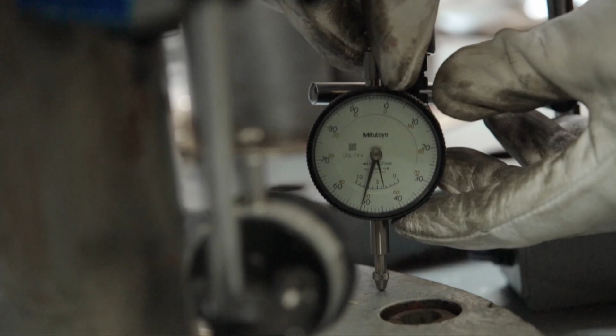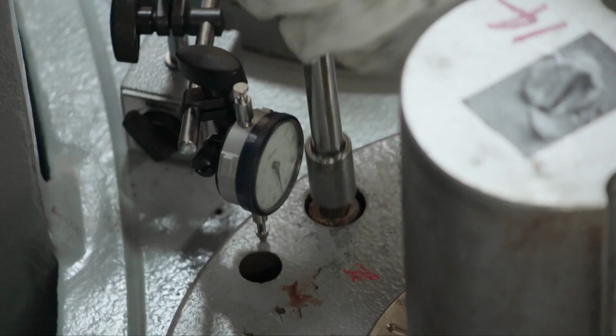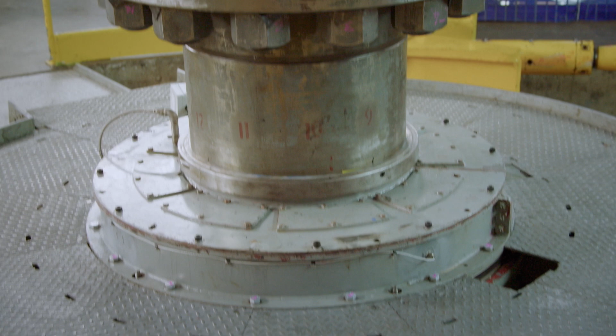We're just measuring the uplift on the reg ring just to make sure that when the 2 hydraulic servos do move in and out to regulate the turbine, that there aren't any issues with the reg ring jumping up and down. So a couple of mil out on this measurement could actually mean that we don't regulate the turbine properly and we could have a runaway event. So definitely not something that we want. But that would then result in the turbine overspeeding. If that happened, then the turbine could actually start throwing itself apart.